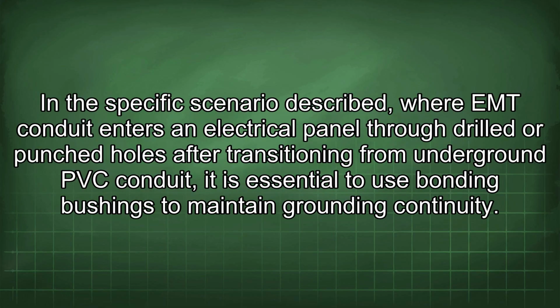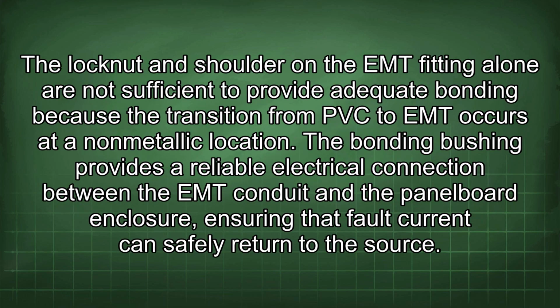In the specific scenario described, where EMT conduit enters an electrical panel through drilled or punched holes after transitioning from underground PVC conduit, it is essential to use bonding bushings to maintain grounding continuity. The lock nut and shoulder on the EMT fitting alone are not sufficient to provide adequate bonding because the transition from PVC to EMT occurs at a non-metallic location. The bonding bushing provides a reliable electrical connection between the EMT conduit and the panel board enclosure, ensuring that fault current can safely return to the source.